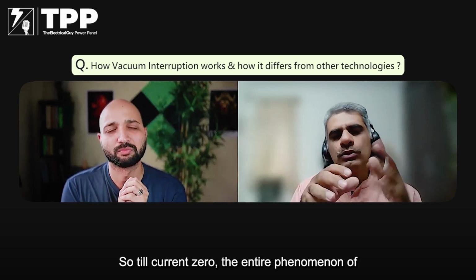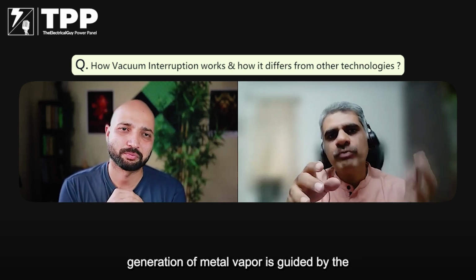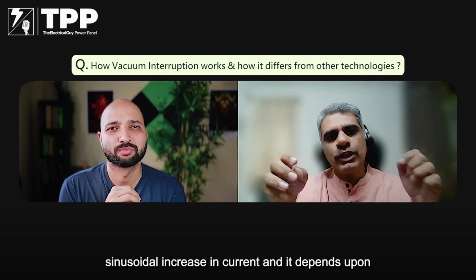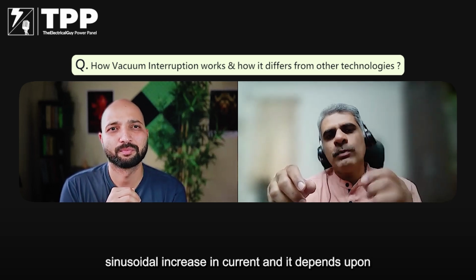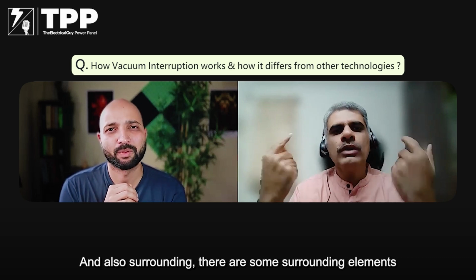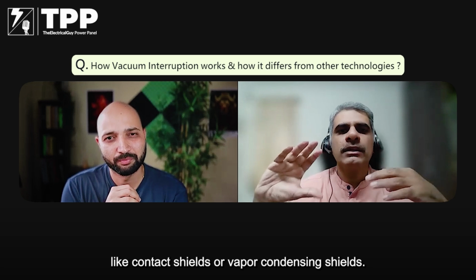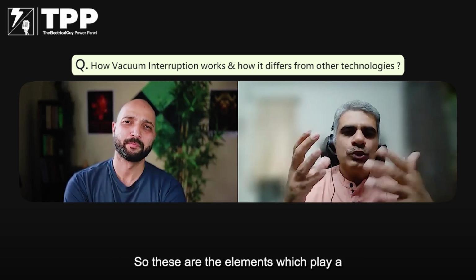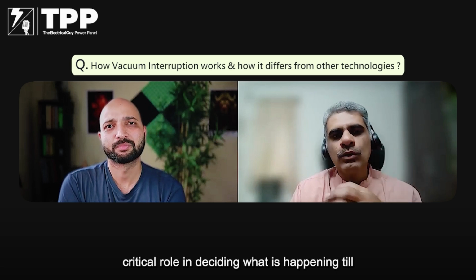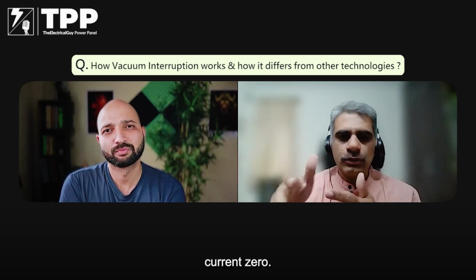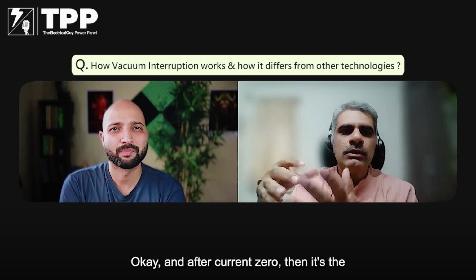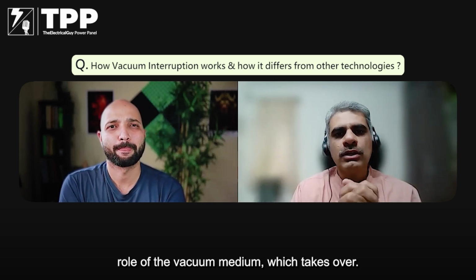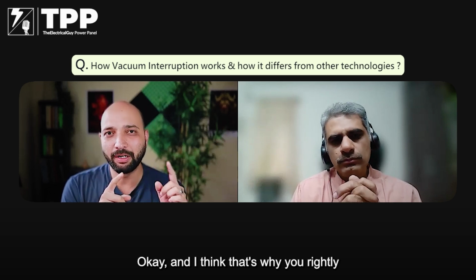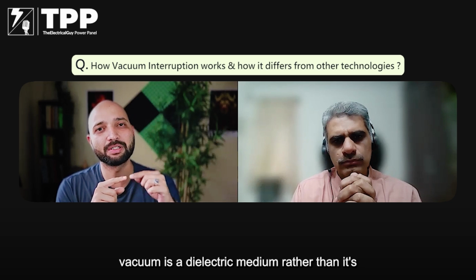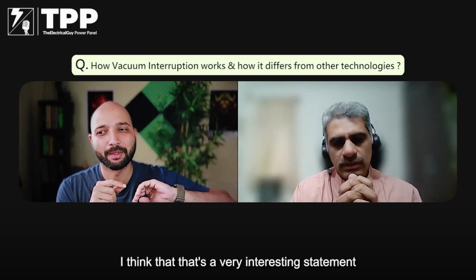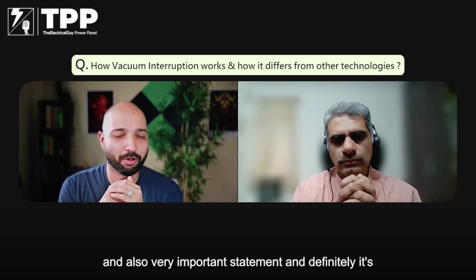Till current zero, the entire phenomenon of generation of metal vapor is guided by the sinusoidal increase in current, and it depends upon the contact metallurgy. And also there are some surrounding elements like contact shields or vapor condensing shields. These are the elements which play a critical role in deciding what is happening till current zero. And after current zero, it's the vacuum medium which takes over. I think that's why you rightly mentioned in the beginning that vacuum is a dielectric medium rather than an interrupting medium. Yes, that's a very interesting and also very important statement.